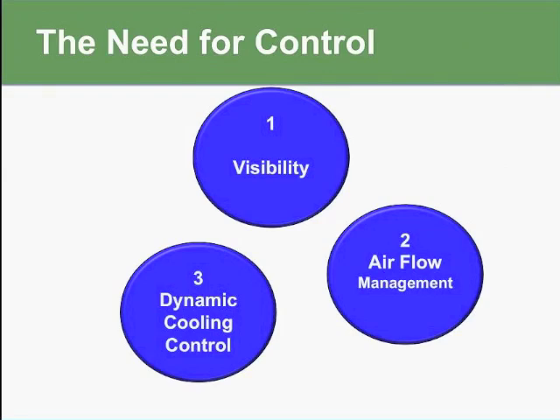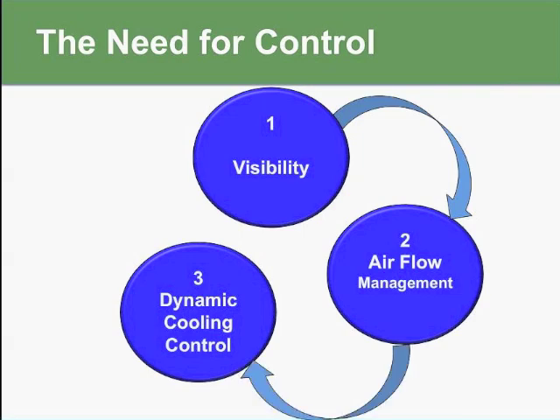So finally, I just want to impress upon you, I'm not a control freak, but in this case, I do believe there's definitely a need for control. If you can gain visibility of what's going on in your data center from a temperature and operational perspective, you can see what you need to do for airflow management. Once you implement the airflow management and the dynamic cooling controls, you'll see the benefits. And as things change within the data center, as things get moved around and new equipment is added and taken away, you still have that ongoing visibility, and you maintain the airflow management and the dynamic cooling.